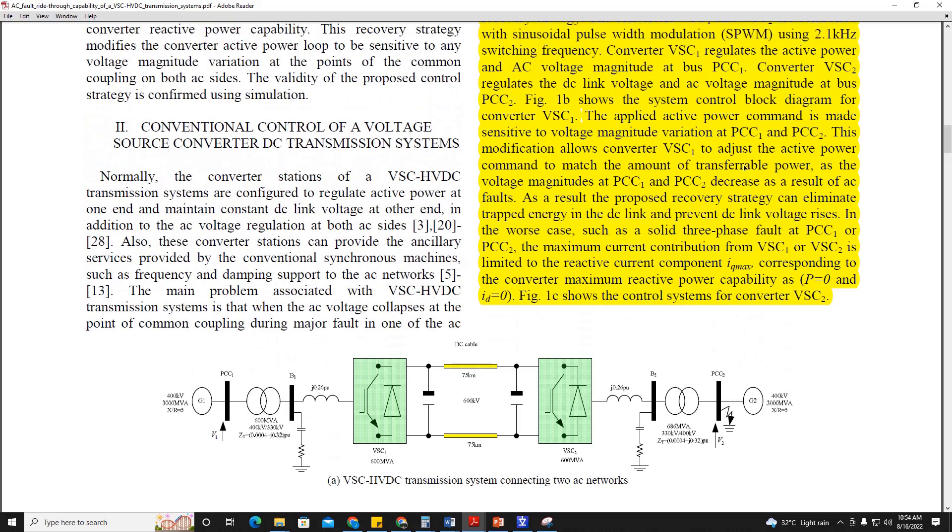And how does it ensure this? The applied active power command is made sensitive to voltage magnitude variation at PCC1 and PCC2. If a fault happens at either PCC1 or PCC2, then active power is related to that voltage magnitude variation. Active power will limit itself, will change itself corresponding to changes made in point of common coupling 1 and point of common coupling 2. If there is voltage interruption at PCC2 or voltage dip at PCC2, then it will assume that the fault has happened and depending upon this fault, the fault will communicate to converter station 1 and converter station 1 will reduce its power.